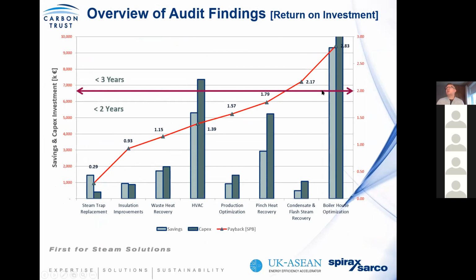Although boiler house optimization can be expensive, what we have found is that customers who did engage us with boiler house optimization projects addressed a lot of the fundamental issues in their steam system, like the separation, effective drainage, the double block and bleed. So they would basically burden the energy efficiency project with what we call system improvements. That's why this figure tends to be high. However, on average, all the projects will give a less than 3-year return on investment. So in other words, these projects are viable and doable within industry.